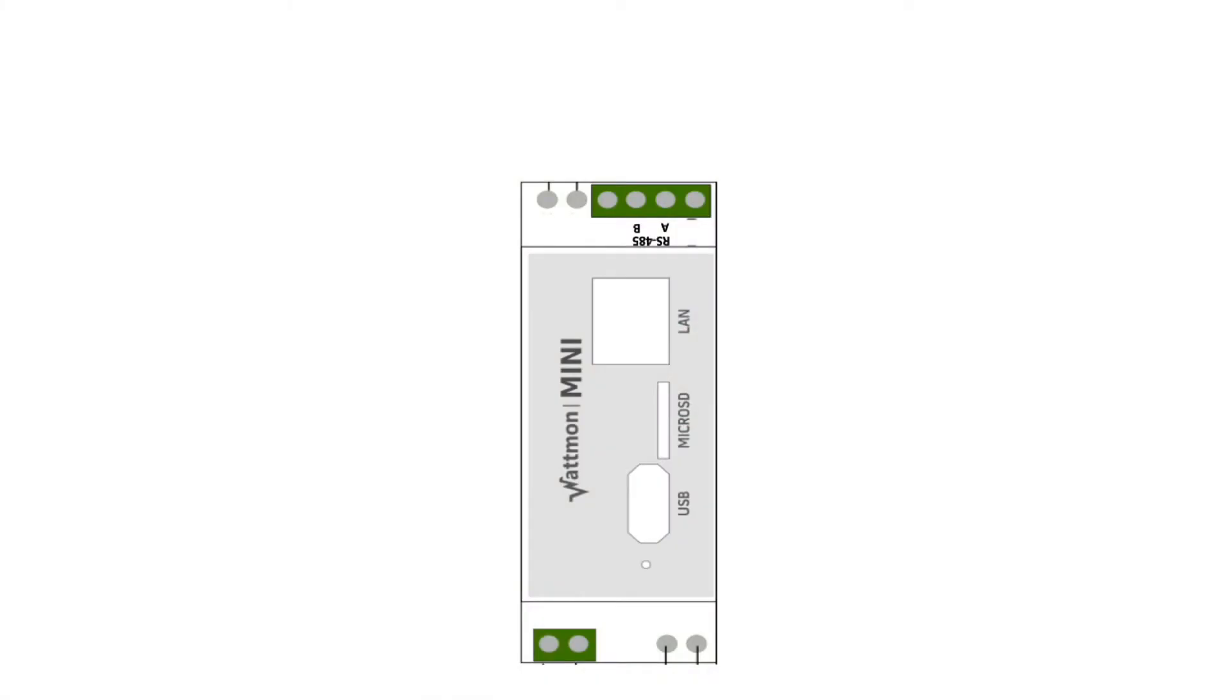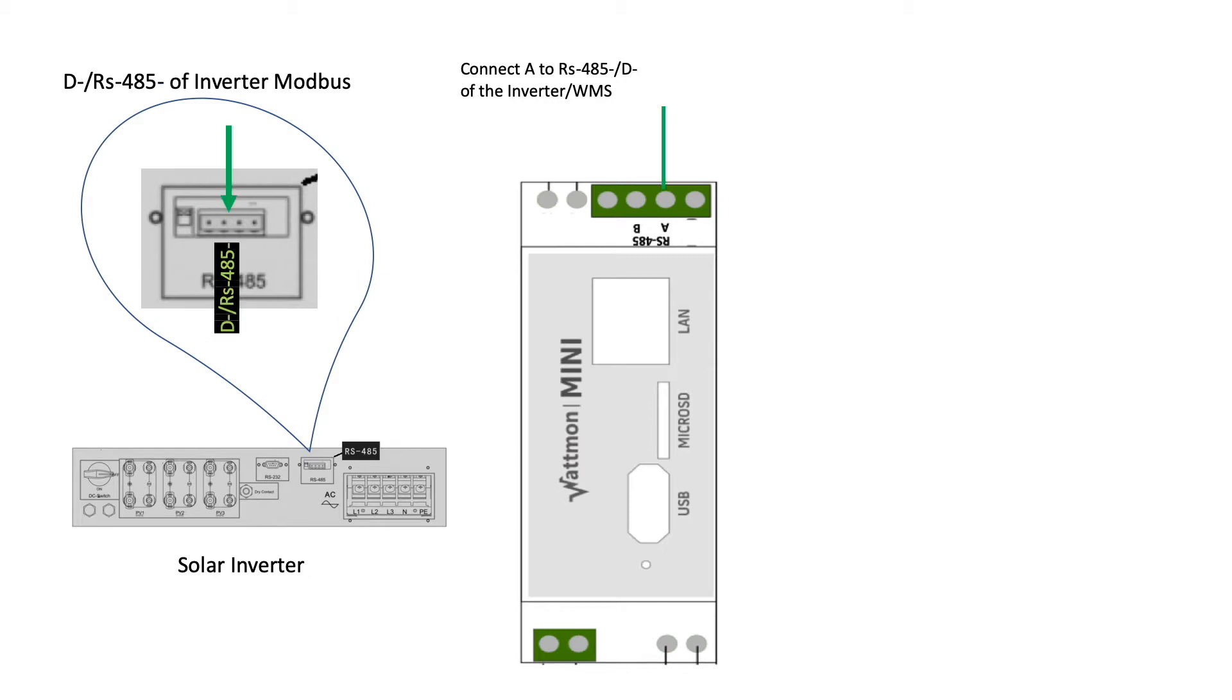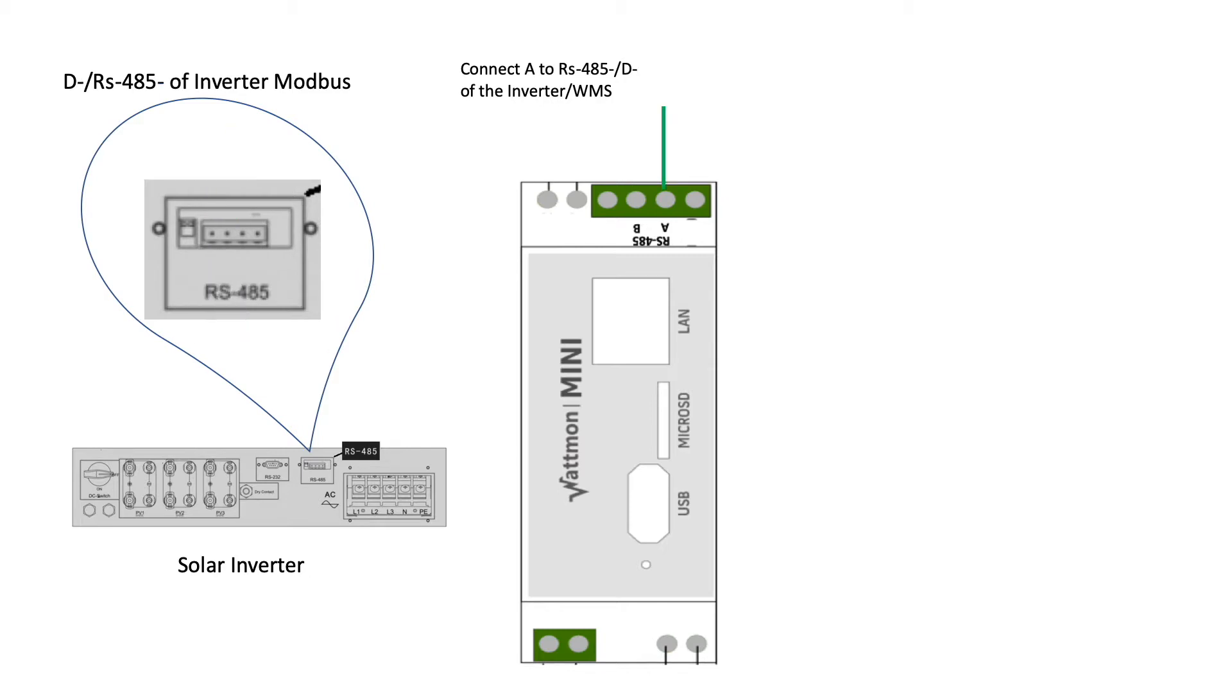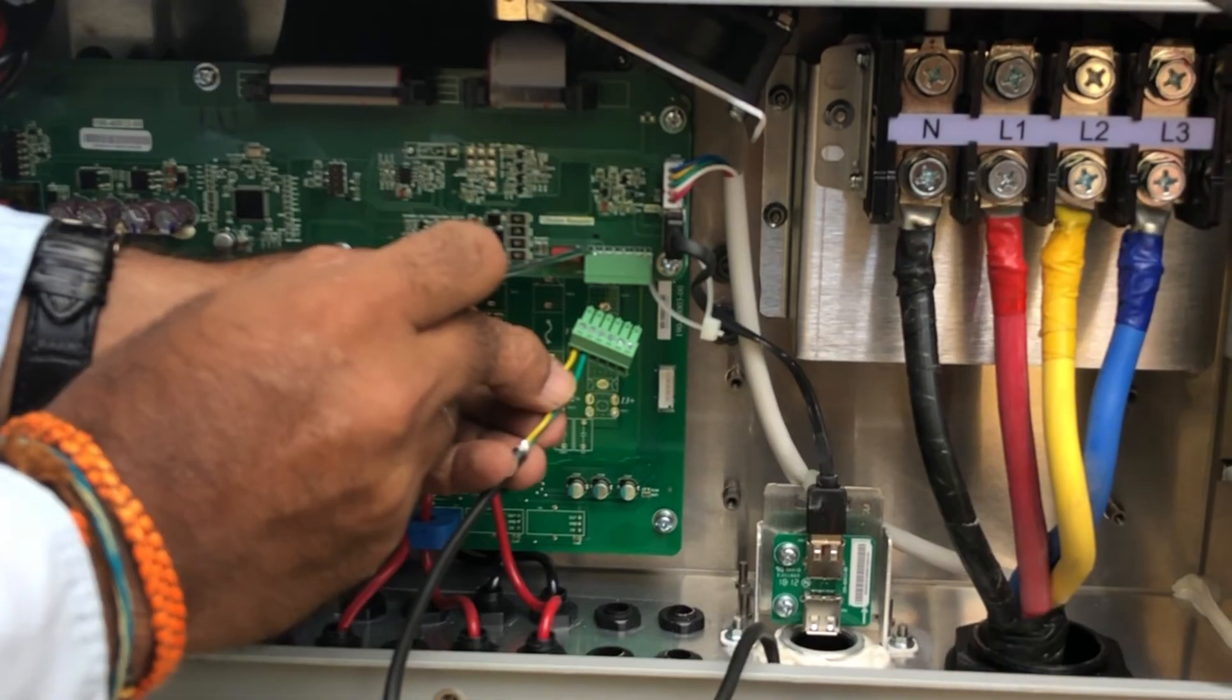On the top end of the logger are RS 485 A and B. B connects to the positive RS 485 and data plus, whereas A connects to the RS 485 minus D minus.